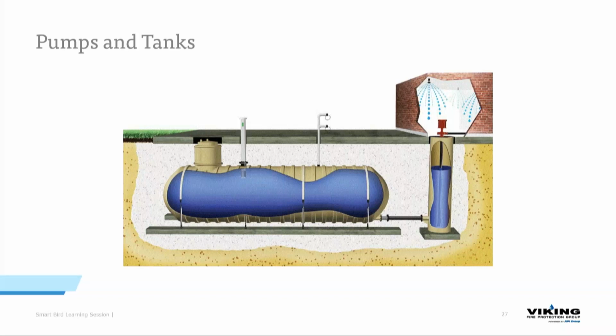We've got a connection to our underground water tank. And underground water tanks do have a lot more considerations to take into account. Sure, they're great because you don't have to worry about them freezing, but we need a fill. I usually recommend some form of extra fill. Hook it up to a well, hook it up to something else, because when you discharge that fire pump, you need to replenish that water within a certain amount of time. Some of that depends on a calculation with the fire department about how long it takes them to get to that facility. So that's always a negotiation of how fast we have to have that filled back up.